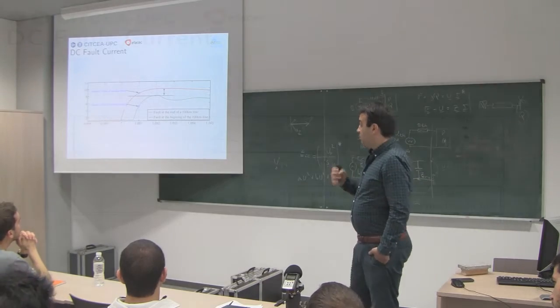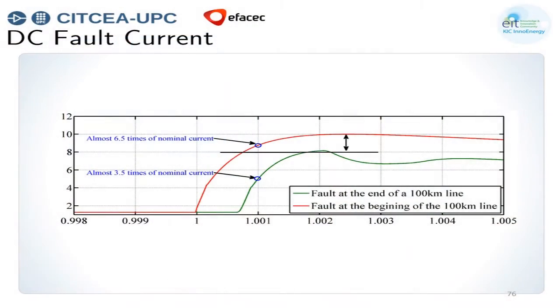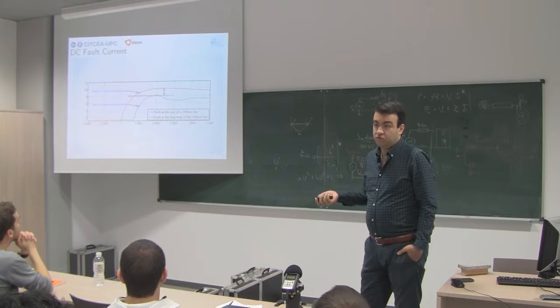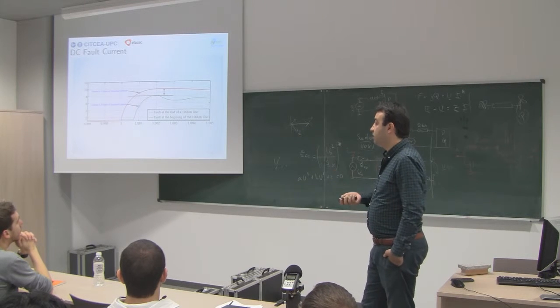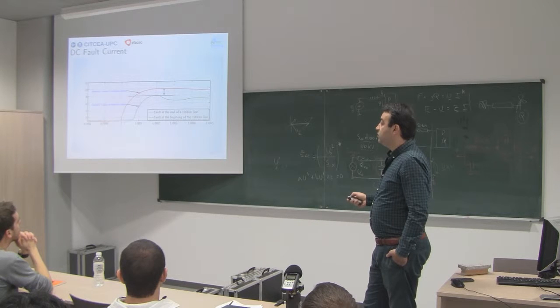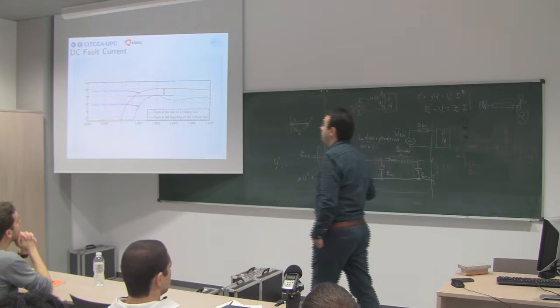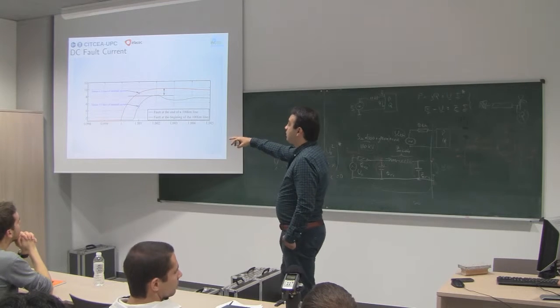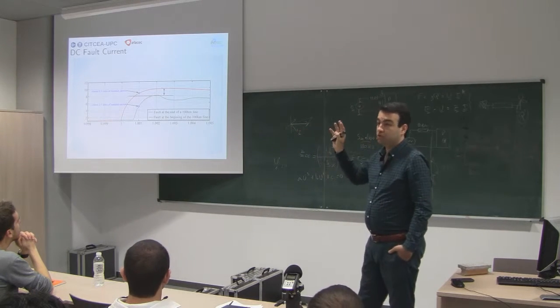And the main point is that the characteristics of this DC fault current are again quite different from the AC one. In AC, the inductors act like impedances, so because of the frequency in your current, they can limit the current both in terms of rate of rise and in terms of peak. But in DC, we don't have such an effect from the inductors. So after inception of a fault, at instant 1, we will have a rapid rise of DC fault current.